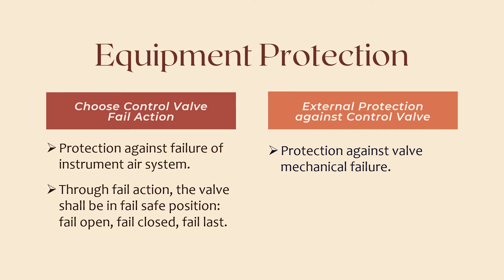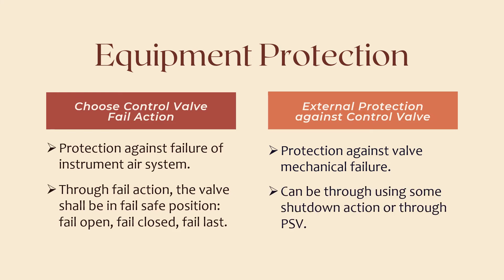External protection can be through a shutdown action, or through a pressure safety valve that shall handle the fluid in case of control valve failure. So if the air supply is cut, the valve should be in fail safe position. This is a parameter that should be considered in the design phase.